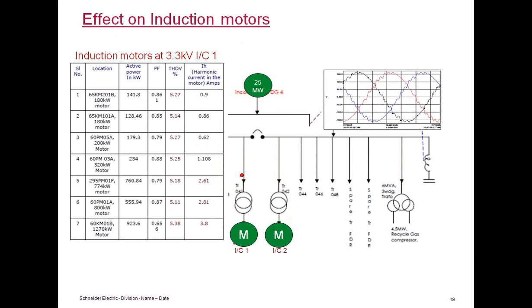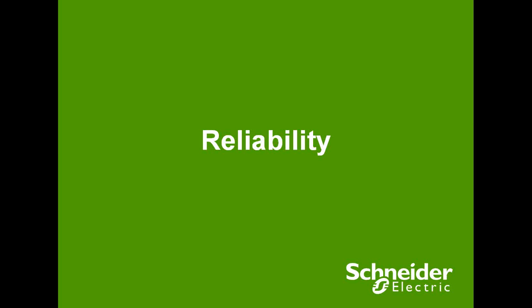So the point is, the harmonic current coming from the 4.5 megawatt drive is just going out to the 11 kV and going into the motors. It is damaging them frequently. So the revenue loss for the customer, number one, is significant, and number two, the breakdown in the production line is also a huge loss for the customer. Reliability.